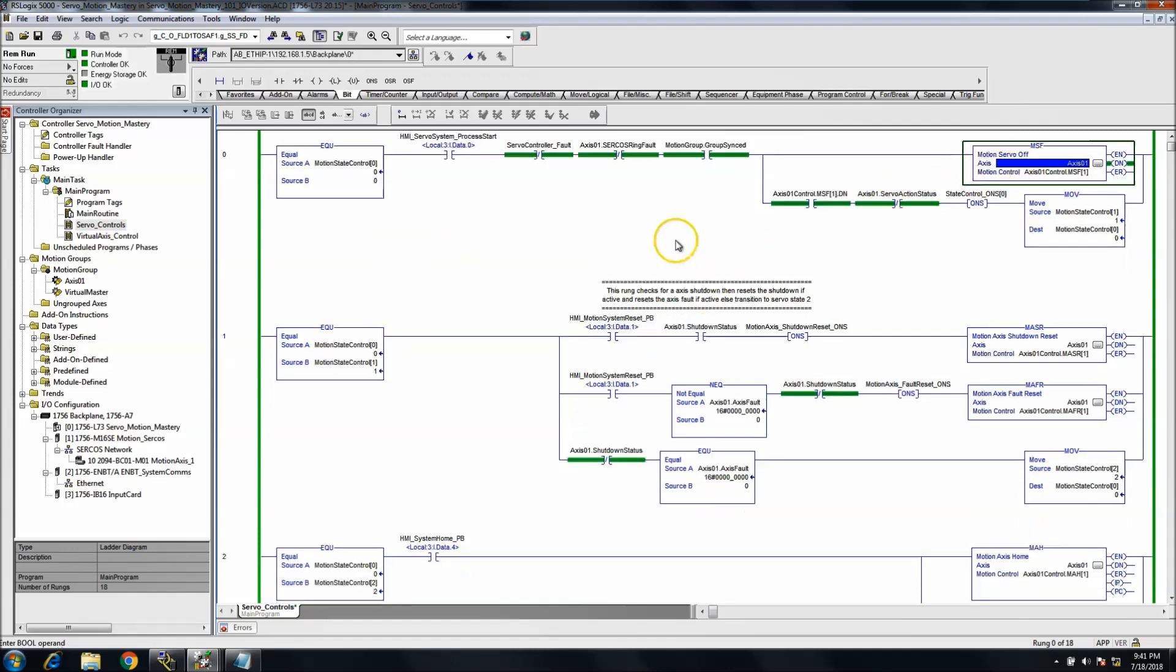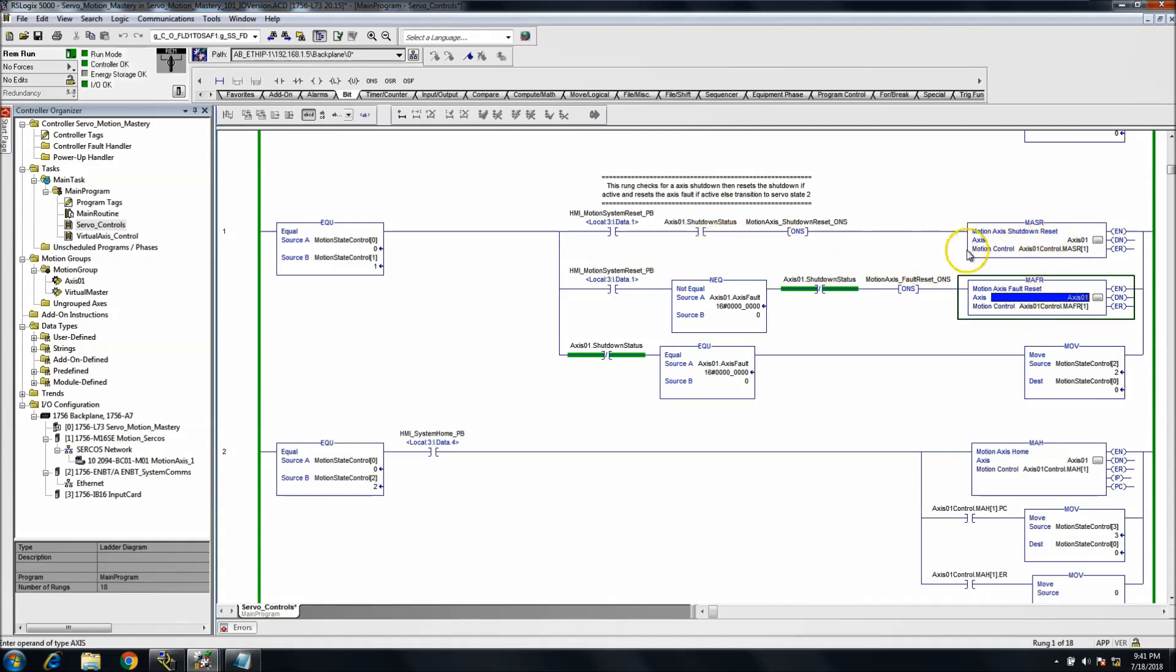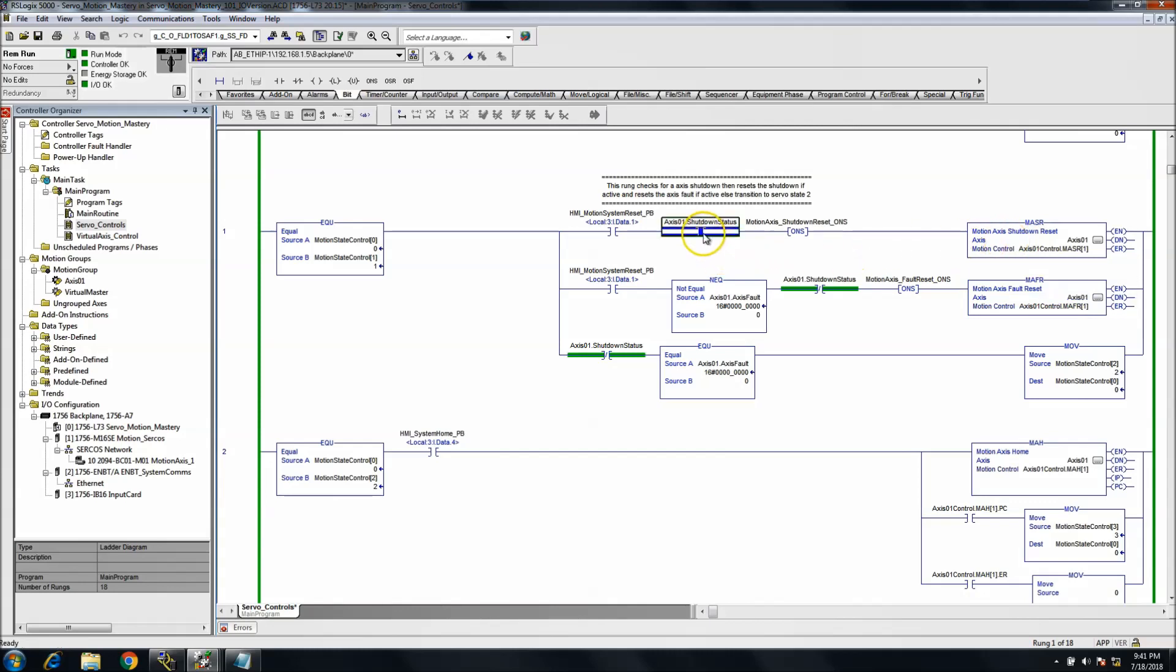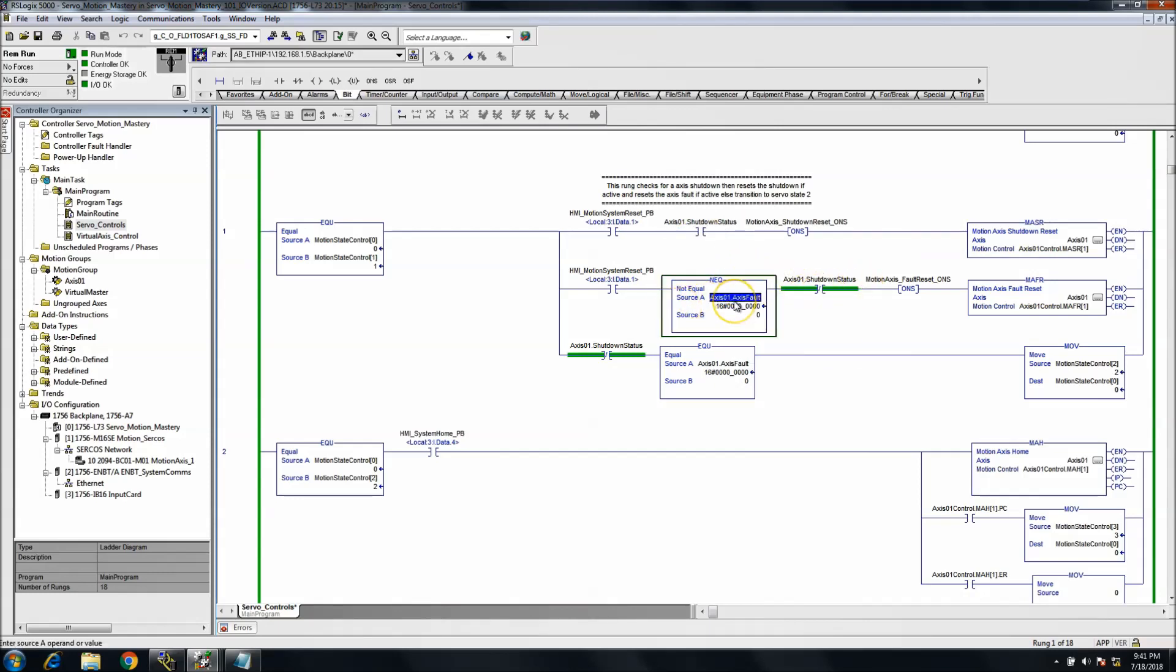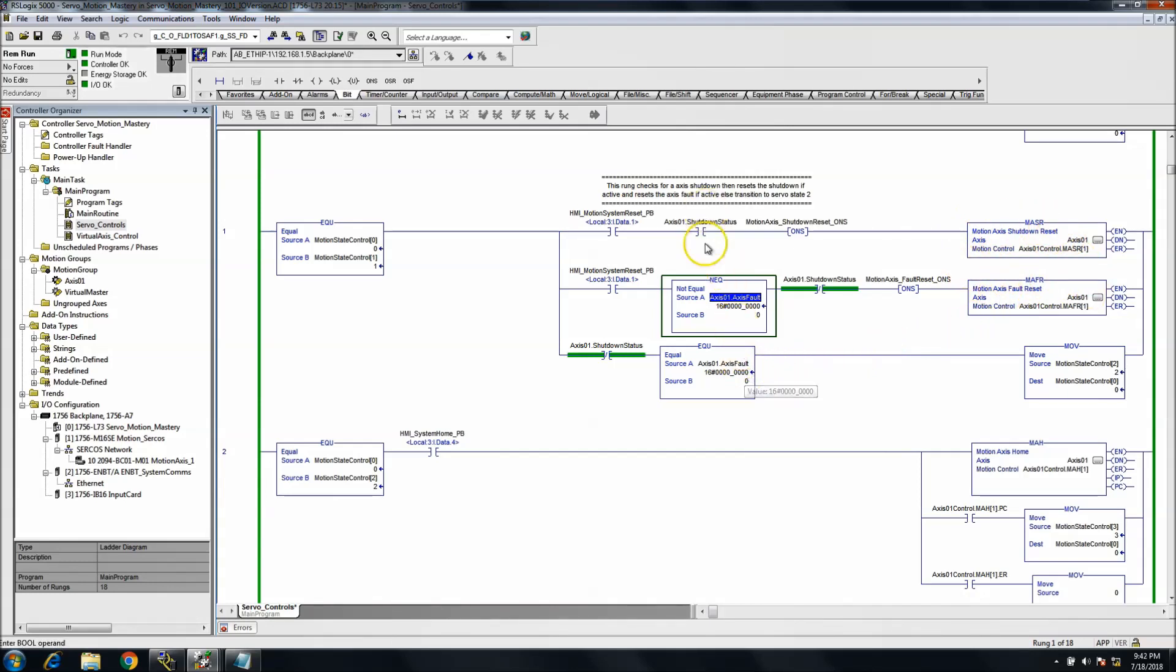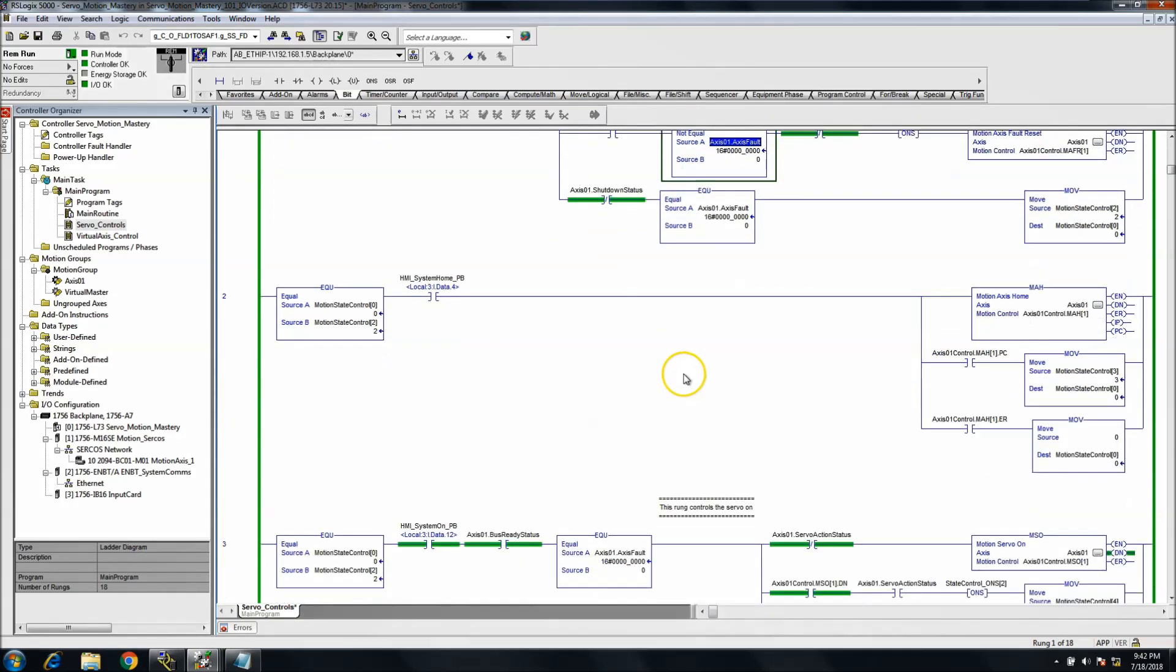I choose to always cut my system OFF first, then I choose to come down here and control a reset. I separate out my resets because if there's a shutdown, like a motion system shutdown, then the shutdown status bit will come on and it will issue the shutdown reset. However, if the shutdown is good and there's no shutdown and the axis is faulted, then I just want to reset my axis. Therefore I'm not doing both of them at one time—I'm only doing the one I need to do.